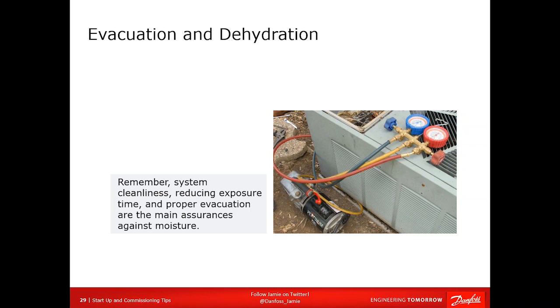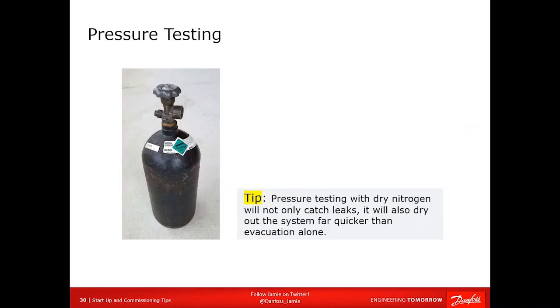Once you unplug it and you put it in the system, before you braze it in, bleed a bit more nitrogen through the system, or keep bleeding it, so you get all that nice dry nitrogen in the area around there. I can guarantee if you do this, you will effectively stop getting any moisture in the oil. And trust me, getting moisture out of POE oil is damn near impossible. It will take a long time through evacuation only.